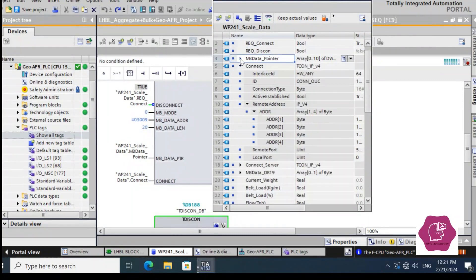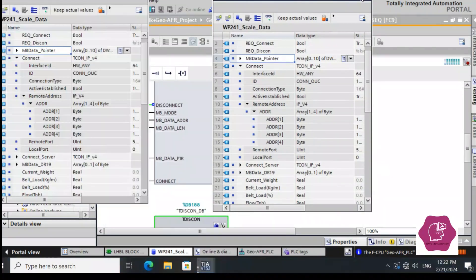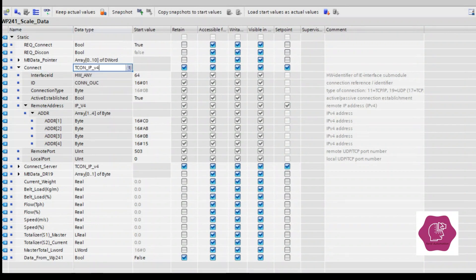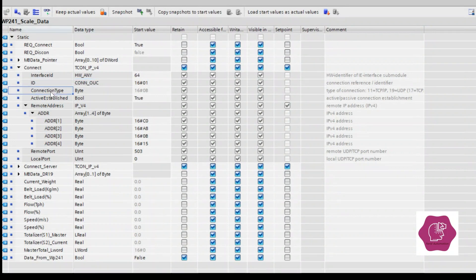Now the connection — this is the TCP connection with the Modbus server. We have to use a TCP tag. We wrote a variable name as 'connect' and gave the data type as TCP connection IP version 4, called TCON_IP_V4. In that data type there is some stack data: Interface ID, communication ID, connection type, and active established.